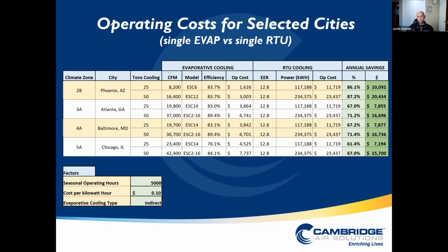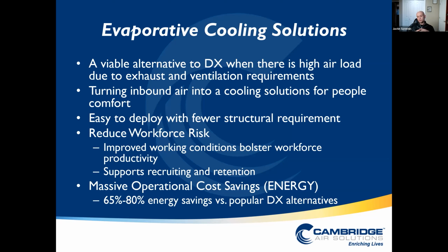One of the best ways to use these evaporative coolers is as a pre-cooler. We pre-cool the air — we can even recirculate and pre-cool it, giving a little heat recovery — and then trim it with a piece of DX equipment. That's what we're doing in our space with this air turnover unit. It costs very little to operate because we're only getting a few tons of cooling out of it versus what it's capable of, 150 tons.